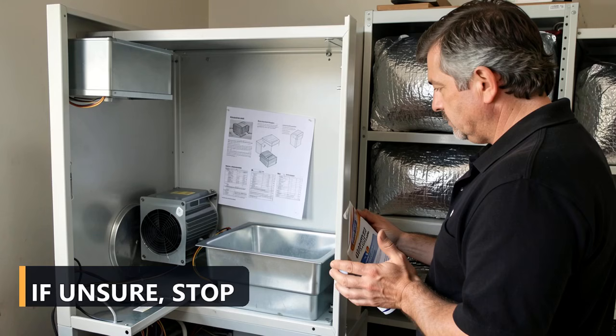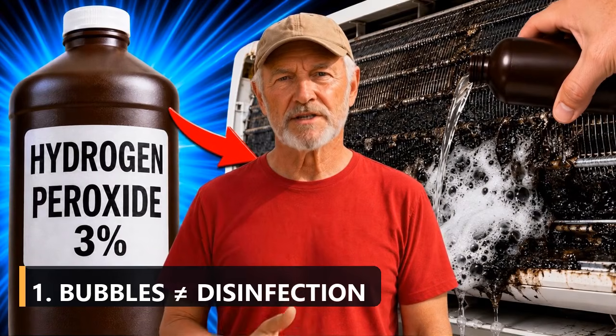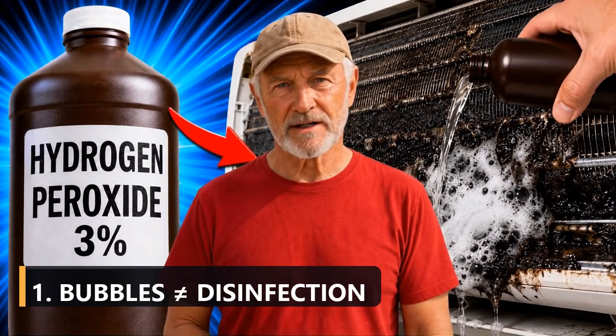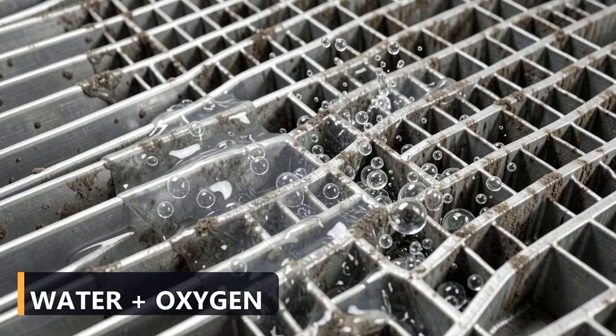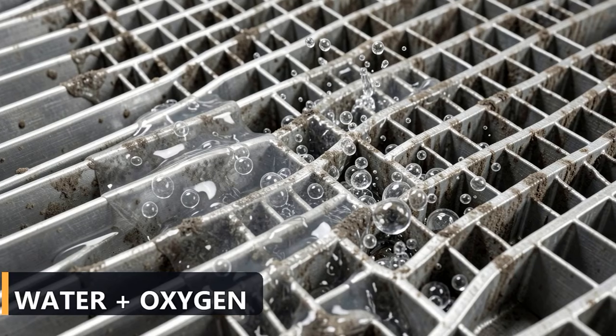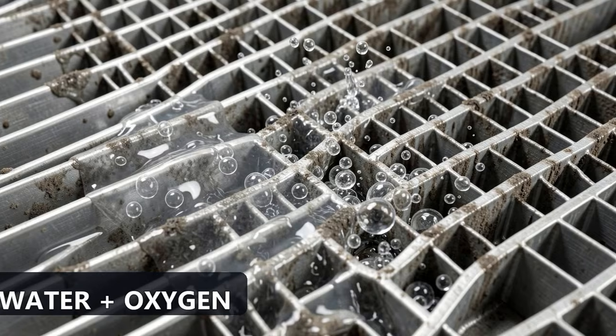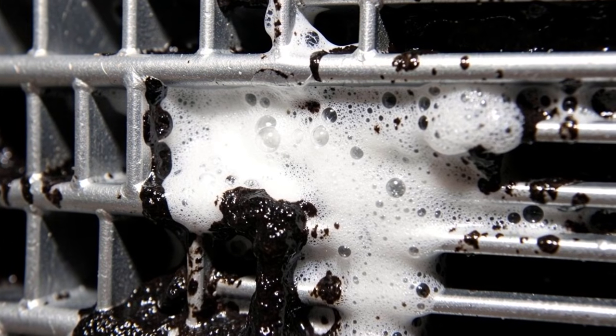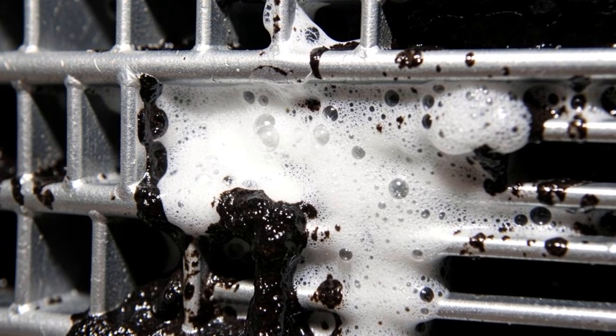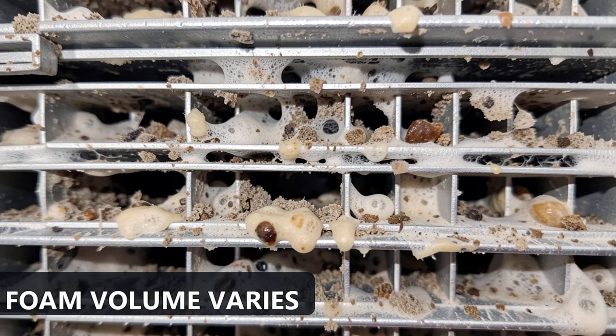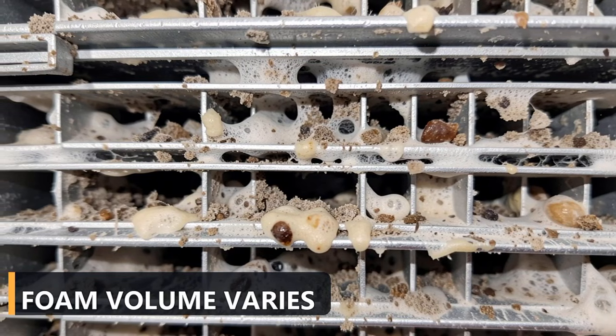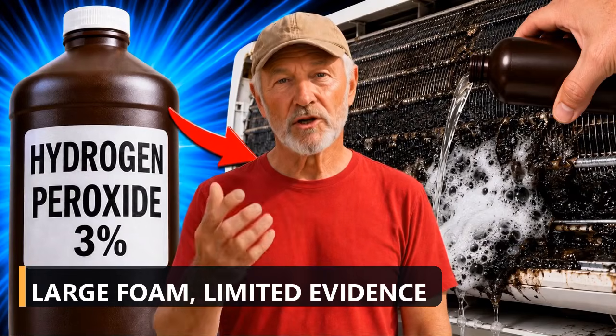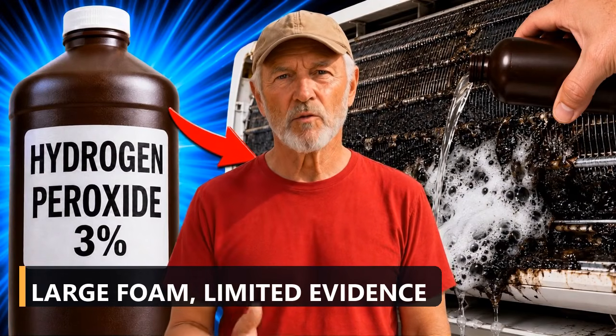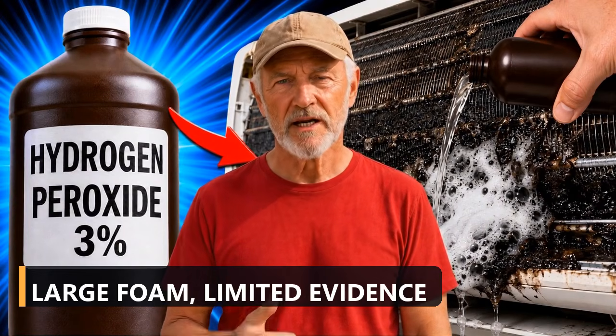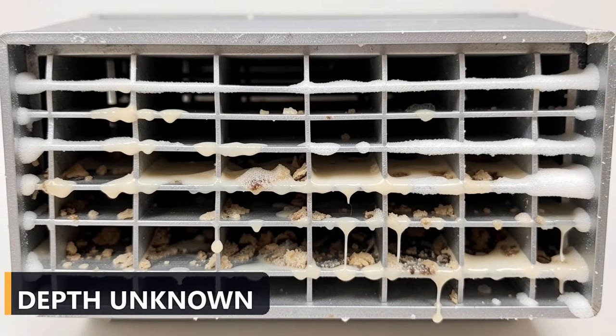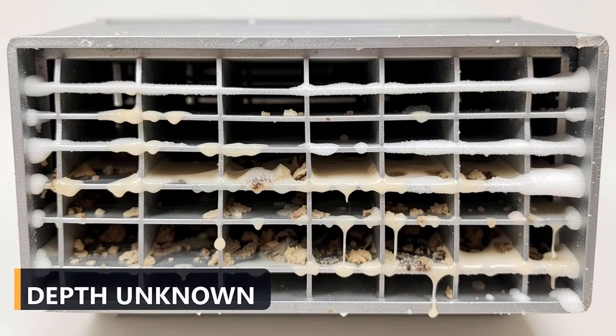Number 1. The bubbles are not proof that the entire surface has been disinfected. Hydrogen peroxide naturally breaks down into water and oxygen. When it contacts certain organic material and enzymes, that breakdown can accelerate, producing the familiar white fizz. On a dirty HVAC surface, trapped air, dust, biological residue, and the rough texture of the buildup can make the reaction look enormous. But the size of the foam does not tell you which organism was present, how deep the contamination goes, or whether every part of it received an effective treatment.